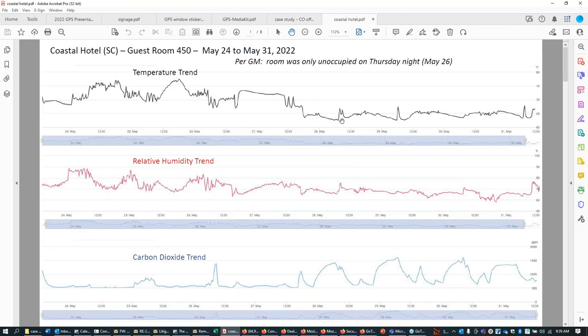Another case study I'd like to share is from a hotel that we did in Charleston, South Carolina, where you can imagine humidity concerns and challenges are really dramatic. This was a temperature and humidity trend from a single guest room, and you can see here the humidity was above 70% for most of this 8-day study. Now, as a result of this excess humidity, there were musty odors in the room, and this was an odor control application, but it also turned into a particle control application with the data that I collected over the 8 days. This room was occupied for the full week except for one night, and I showed the temperature, humidity, and carbon dioxide as our typical IAQ parameters that we look at.